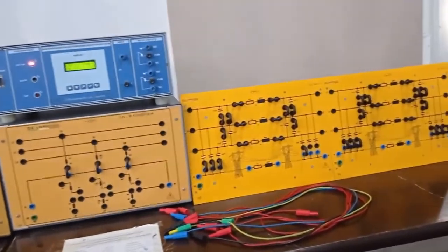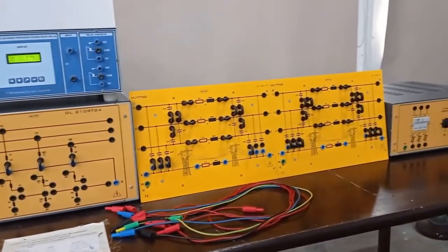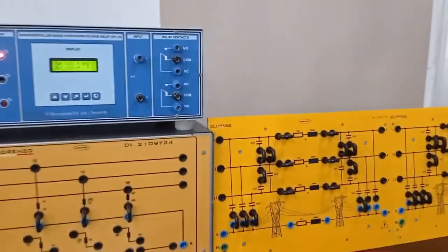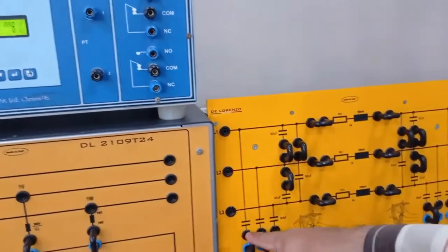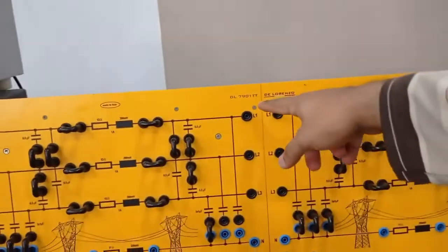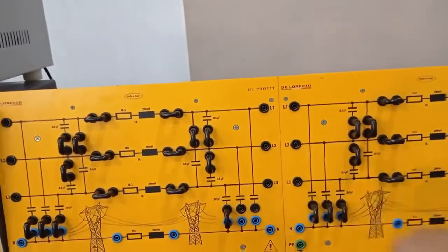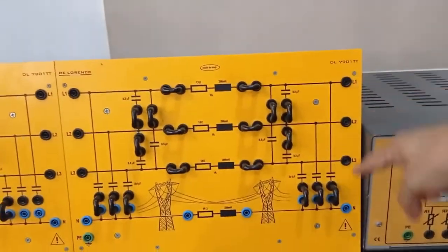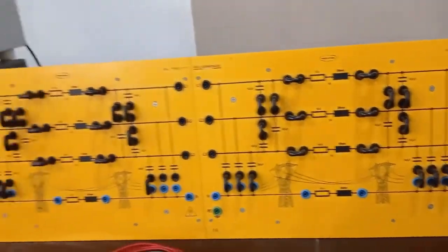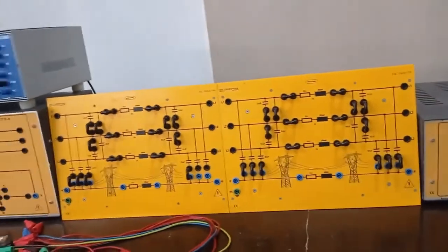So the ground fault will be inserted at 3 different locations. The first location is this one, line 1 to ground, fault 1. Fault 2 will be here, at the midpoint of the line, and fault 3 will be at the remote end of the line. So this experiment will be repeated in unloaded and loaded condition.